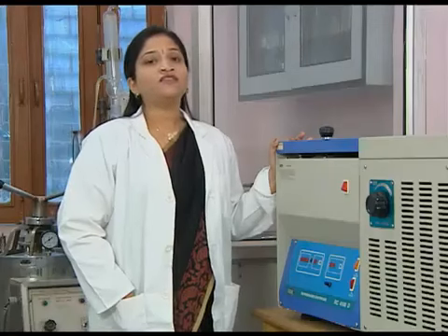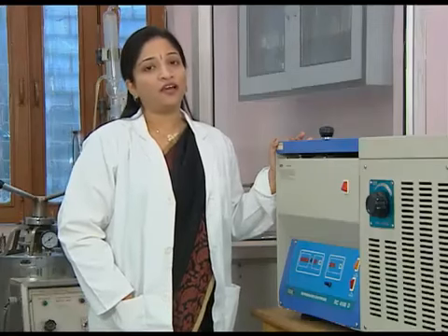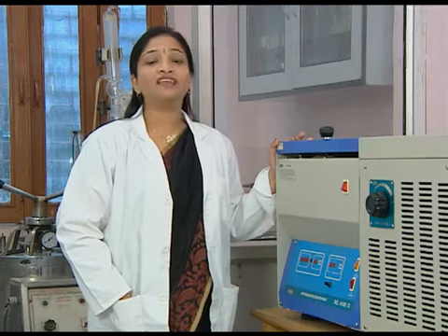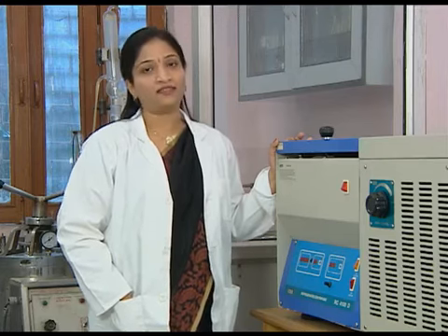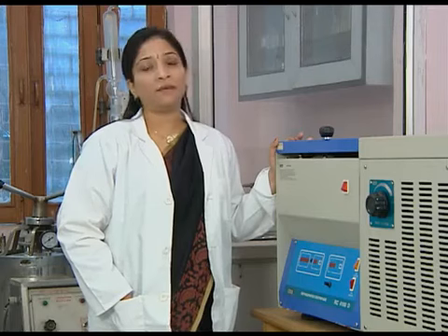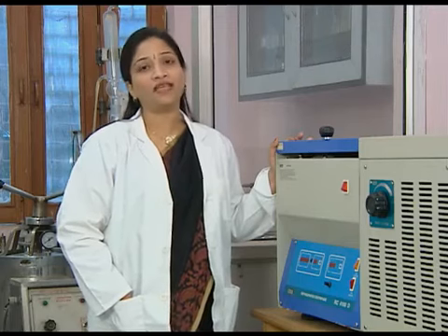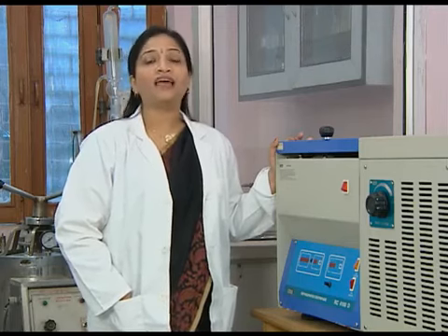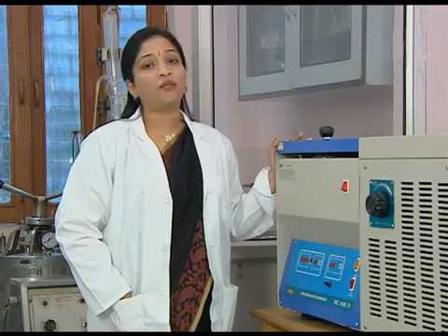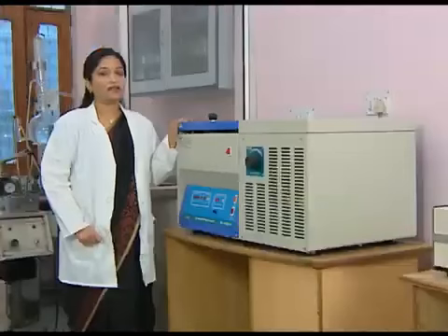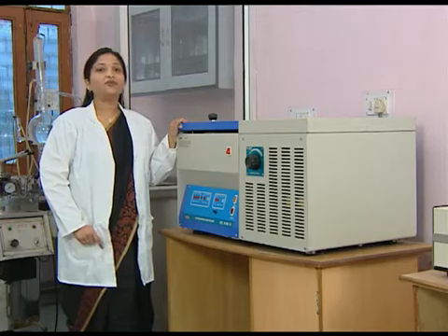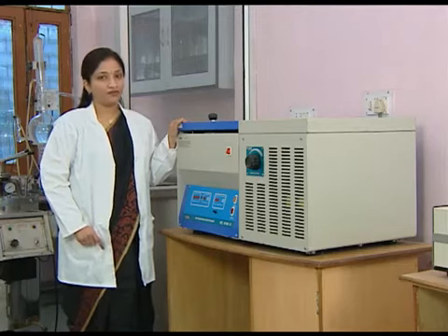The very important criterion that has to be taken into account is the balancing of the device. The amount of the sample, that is the density of the sample, should be equal and it should be placed opposite to each other. Now, I have given you an overview of the centrifuge.